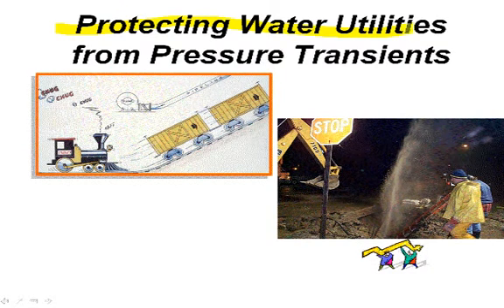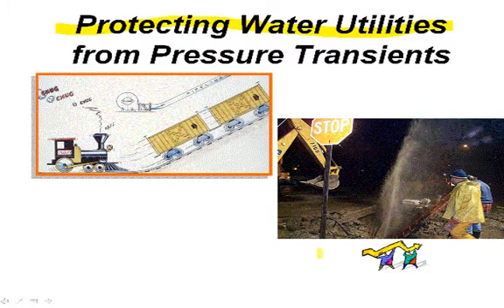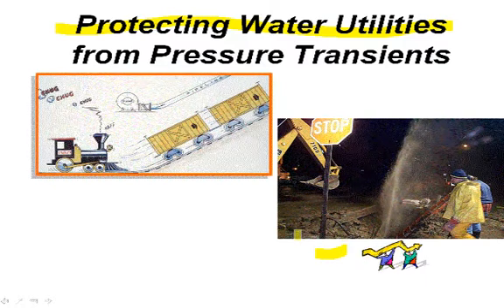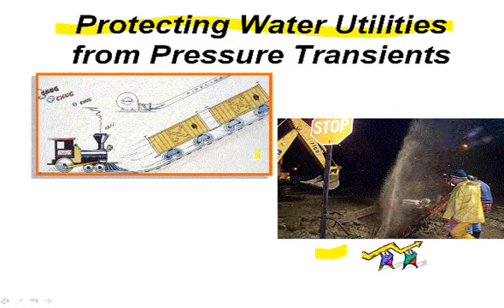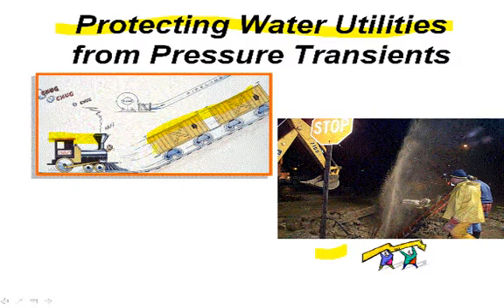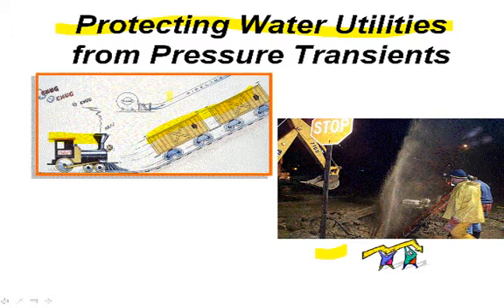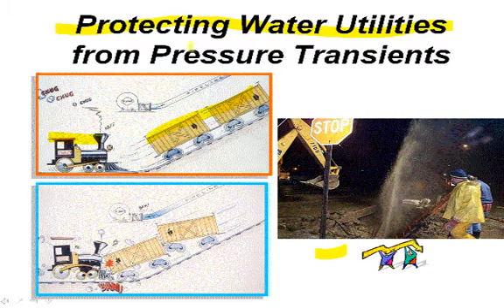I'm going to talk to you about protecting your water utility from pressure transients. Pressure transients are sure to occur in your water system. For example, if you have a pipe break, you'll get a downsurge and low pressure transients and perhaps high pressure transients to follow. A very common situation in a water utility is shown here in this cartoon, where the engine represents a pump and the train cars represent the water. If the pump fails, due to the inertia of the water, you'll get a very large downsurge of pressure, and that will immediately be followed by, due to gravity, the flow reversing and you get this upsurge as shown here.